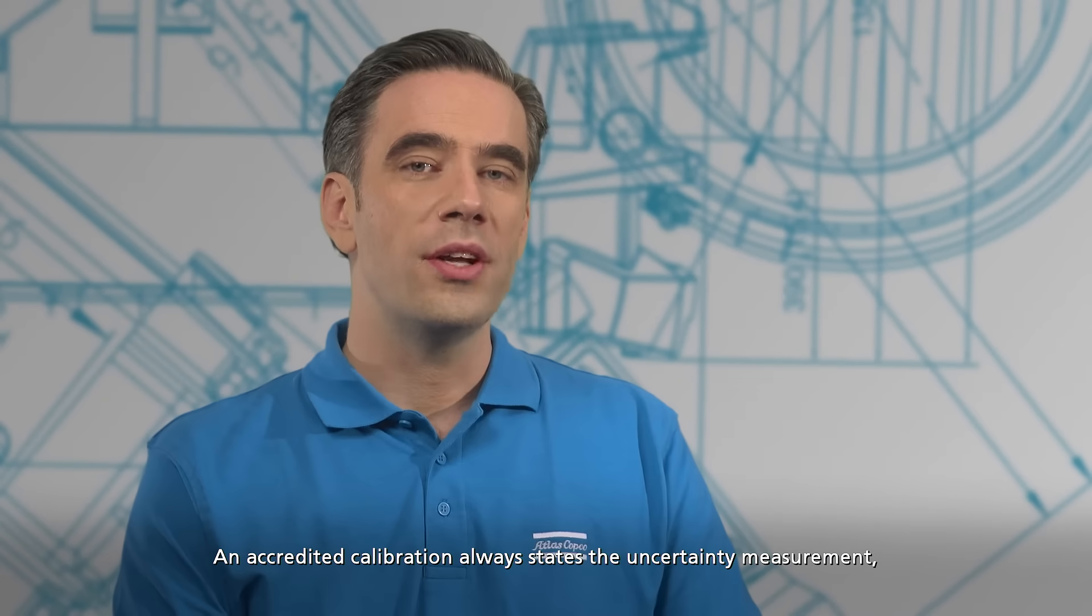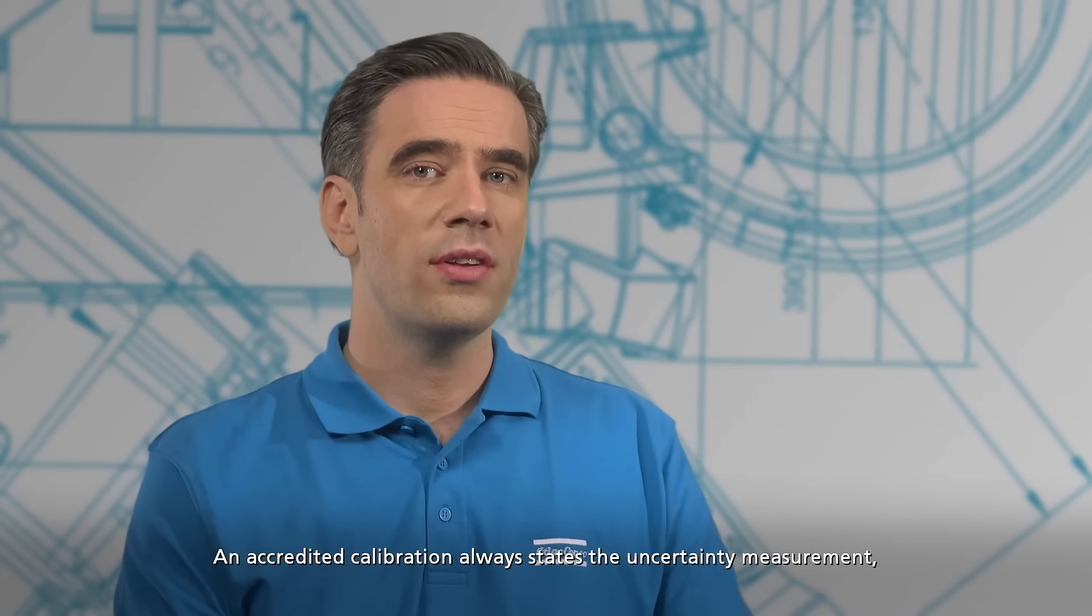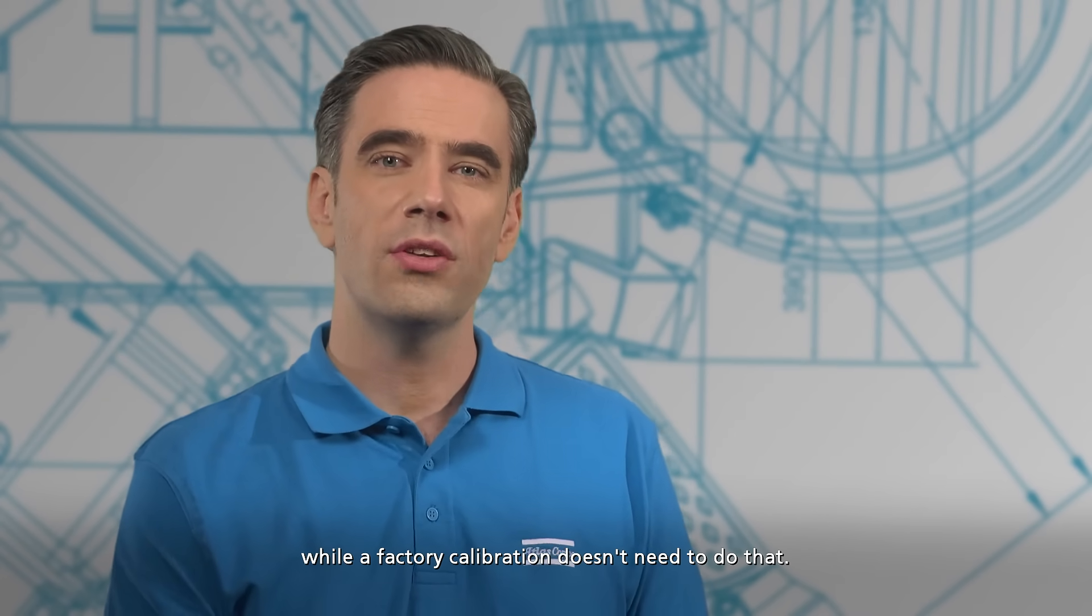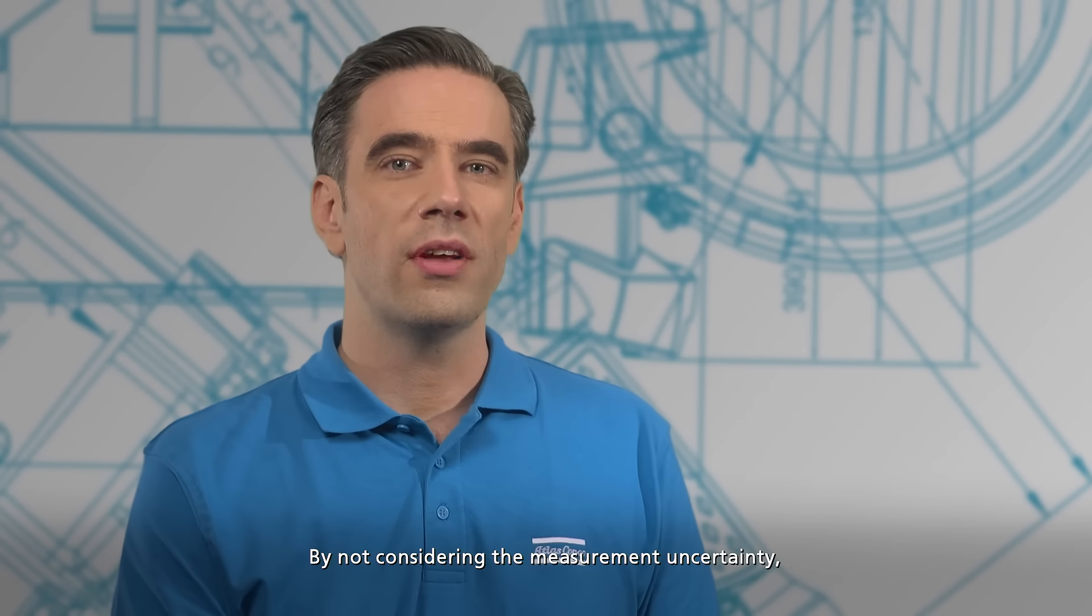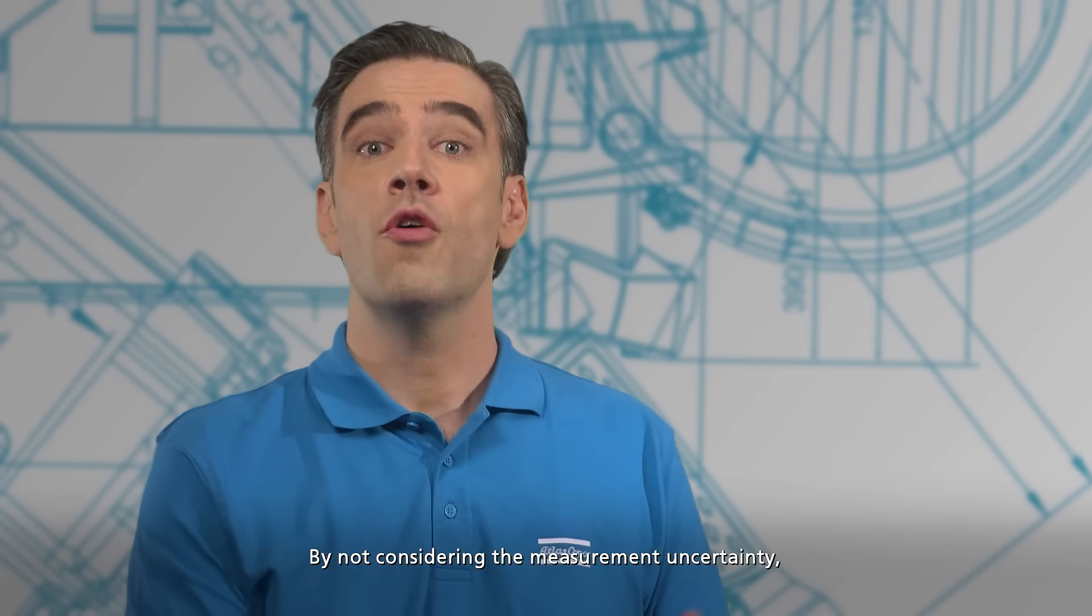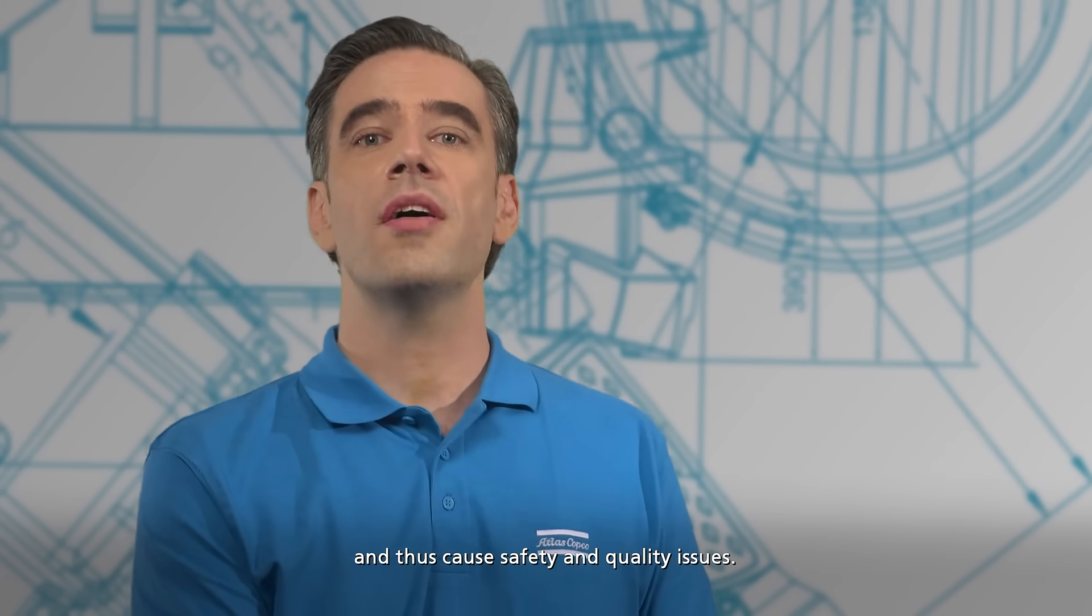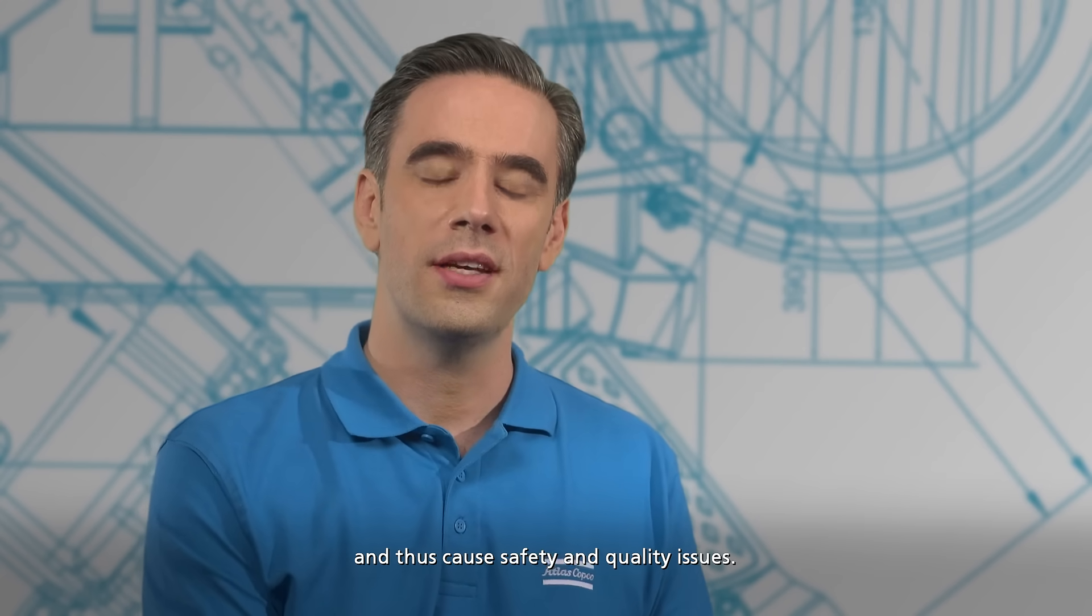An accredited calibration always states the measurement uncertainty, while factory calibration doesn't need to. By not considering measurement uncertainty, faults and errors may remain undiscovered and cause safety and quality issues.